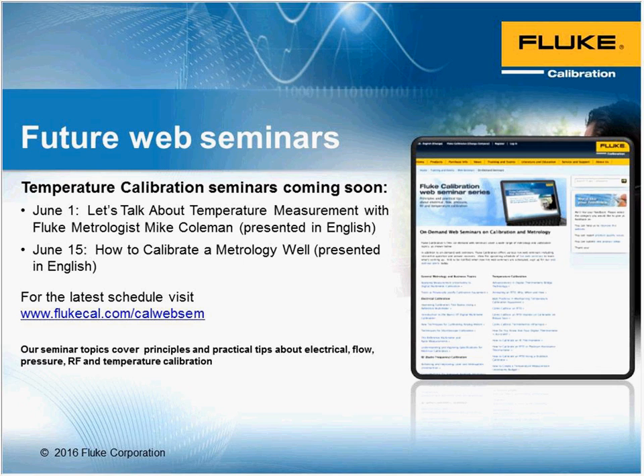Another question from PM2. What is the time to stabilize when changing the data point between 0 degrees and 100 degrees for a dry well? It will be specific to the dry well and the capacity of the unit. Some of our units that have fairly large capacity can move rapidly between temperatures, taking just a few minutes. The smaller ones that go both hot and cold may take a little bit longer. That's an effect you can look for with dry wells. Usually I'll say look at the time from ambient to max temp or from ambient to min temp and base your time on those.